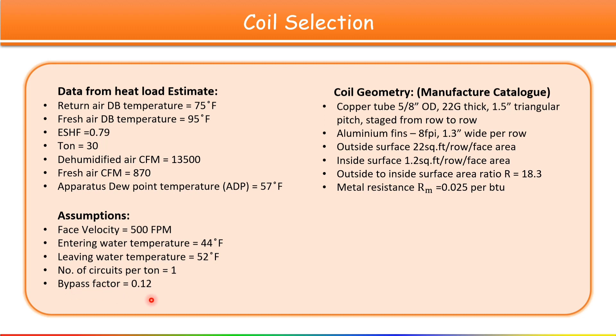Number of circuits per ton we assume as one. Bypass factor is 12% — this is the air which does not touch the coil and enters the room, called bypass air. As per AHRI (Air Conditioning, Heating and Refrigeration Institute), bypass factor should always be 10 to 15%, so I have taken the average value here.